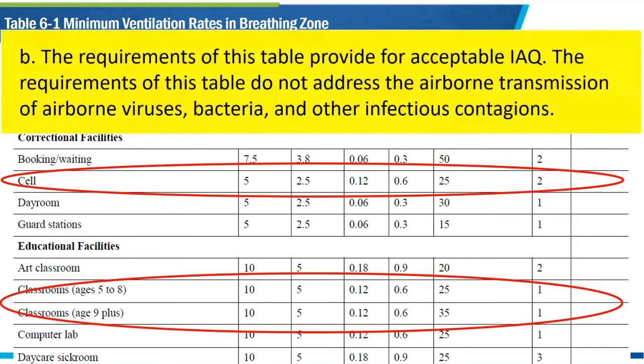I've highlighted note B at the bottom of the table that states the requirements of this table provide for acceptable indoor air quality. The requirements of this table do not address airborne transmission of viruses, bacteria, and other infectious contagions. And that's too bad because we could really use some guidance and direction on how much is enough.